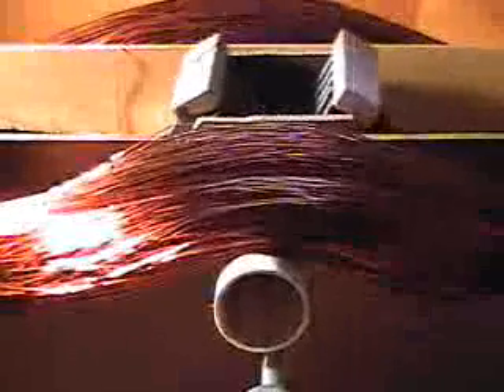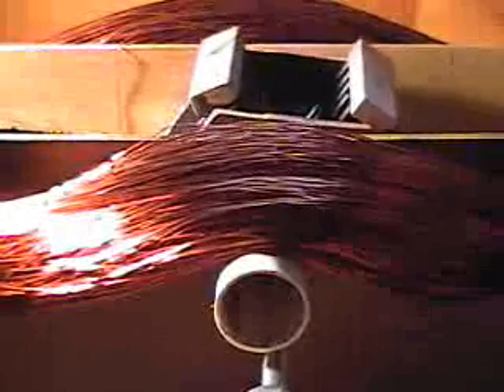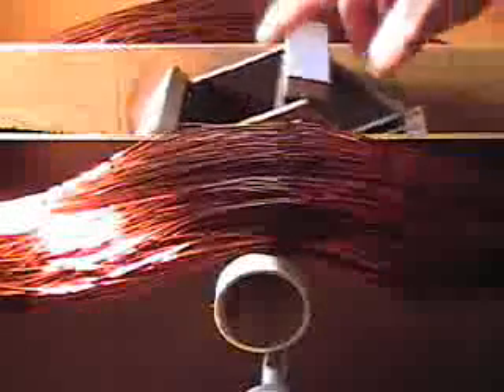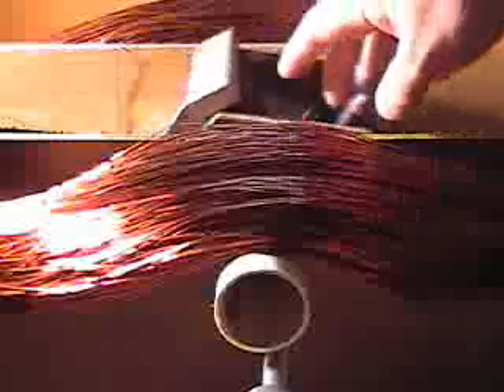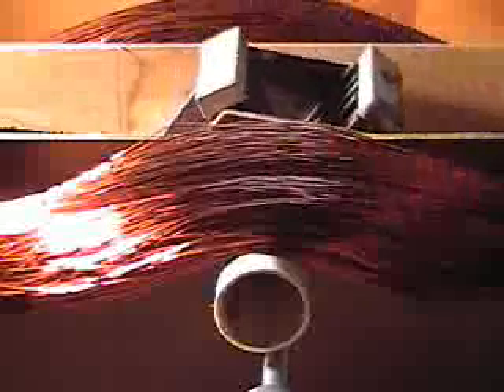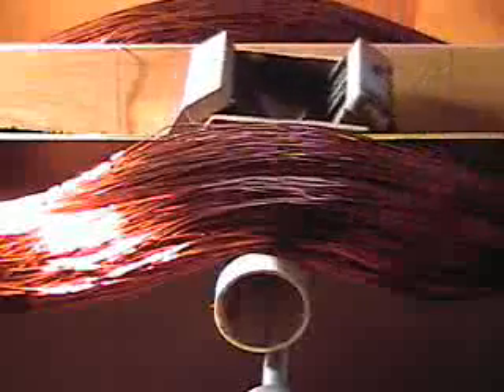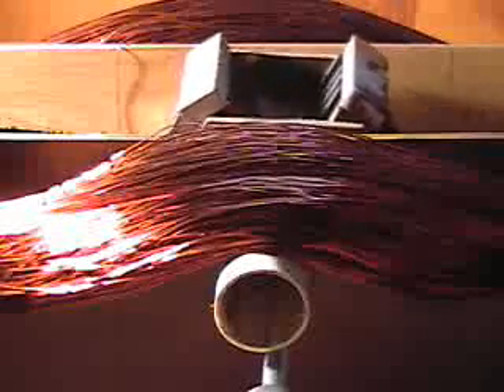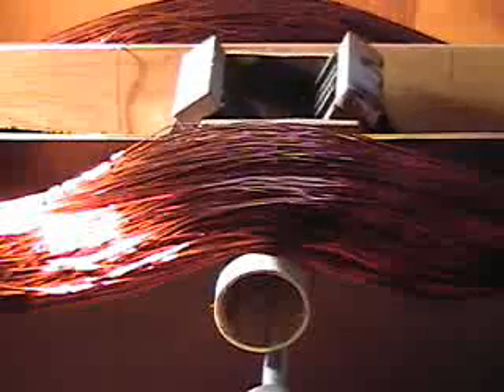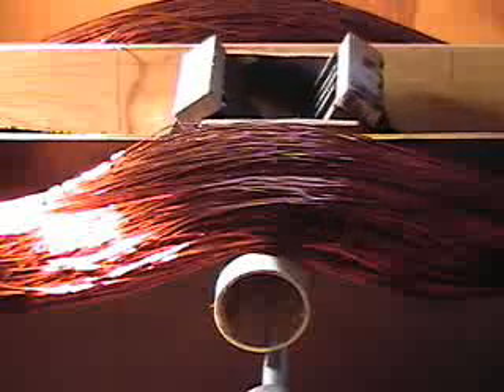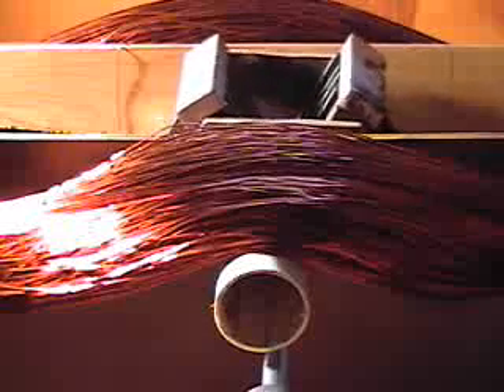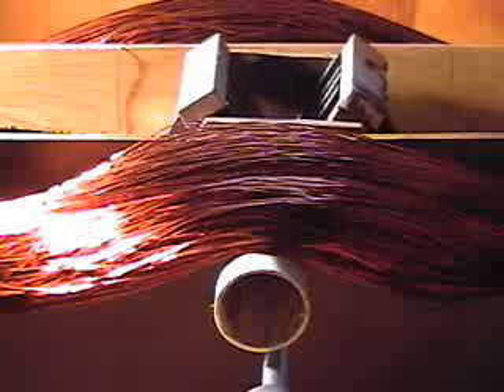As you can see, the design of the rotor here, I'll go in a little closer. It's on a metal file box, and that's why it's kind of circulating at one spot, with a set of nodes where it stops at a certain spot. Doesn't cause too much of a problem, but of course anytime you have a magnetic field going through something like steel, it generates electric current which causes an IR loss. So anyway, I think I'm doing pretty good.